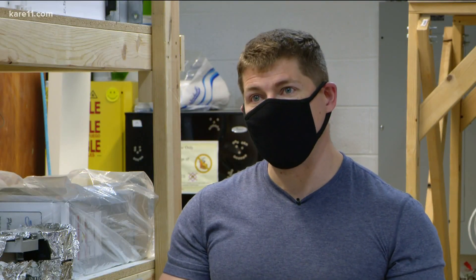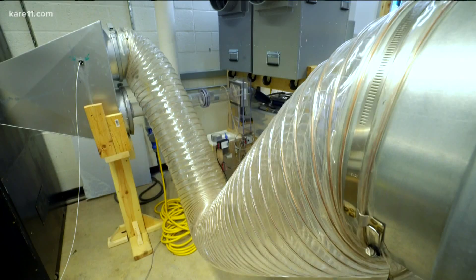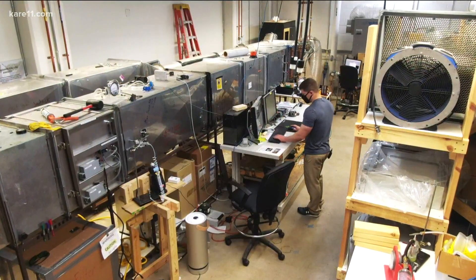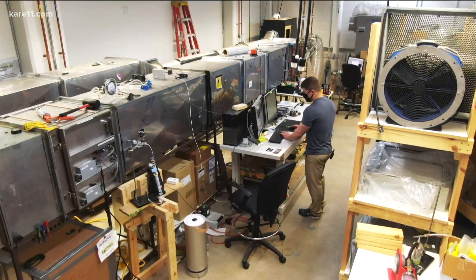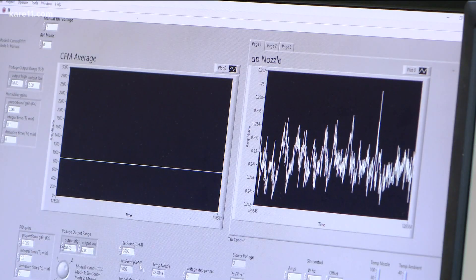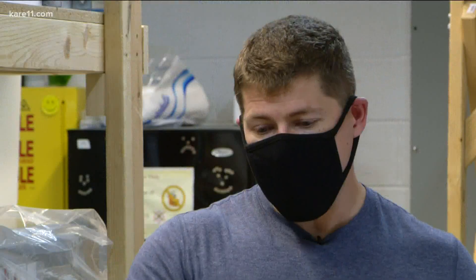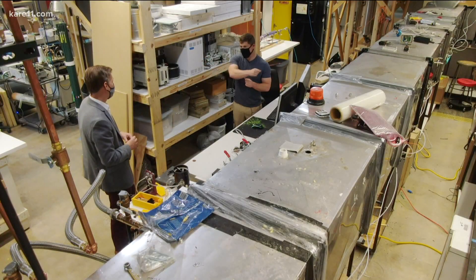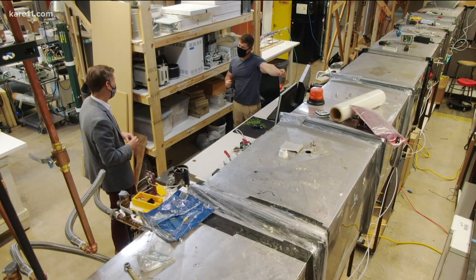This is designed to look at the technologies at scale. And he says one technology has shown to be effective in all kinds of settings. They did a study looking at what's called in-duct UV — that is UVC light inside a duct where airflow passes through. Only one out of every 10,000 viruses that went in was still infectious at the outlet.